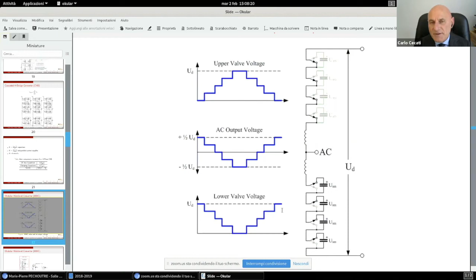So if we have high power demand, in addition to putting modules in series, we can put other modules in parallel. Of course, each module must be paralleled with another one with exactly the same characteristics, specification, and behavior. Otherwise, we will introduce some circulating currents.